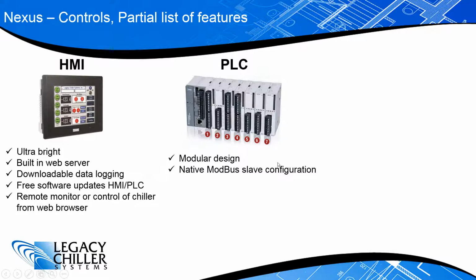We publish all of the Modbus data points through a download, so you can see the table. Very helpful. We do offer BACnet integration, though you'll have to purchase an optional BACnet to Modbus gateway. We have many customers who are communicating via BACnet these days. It also has a built-in SMTP server.